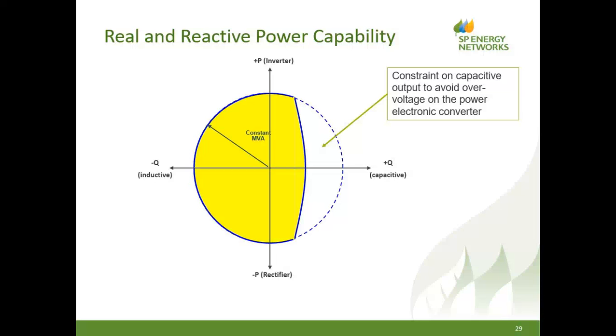But the reality is that the MVDC link can operate anywhere inside the characteristic you see in this slide, the yellow-shaped area. So we can have full power and zero reactive power, or we could absorb full reactive power and have zero power transfer. So if for any reason we don't want to transfer power between the island and the mainland, we effectively have two STATCOMs at our disposal, one at either terminal. If the cable is faulted for some reason, has to be taken out for maintenance or repair, again, we have two STATCOMs, one at either side, which can be operated simply by isolating the switches, which Kevin showed in one of his slides. So the functionality of a voltage source converter is to give both real and reactive power control on the system.